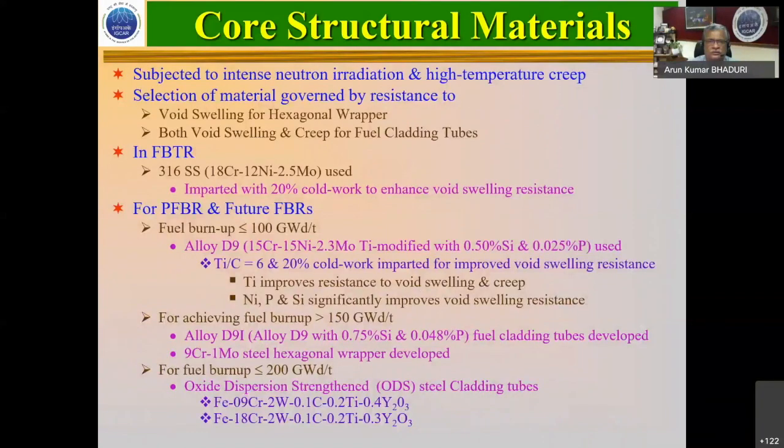The major problem with the core structural materials is that they see high temperature and creep, but also very intense neutron radiation, leading to significant radiation damage — void swelling in the wrapper, irradiation creep, and thermal creep in the fuel cladding. The FBTR, set up with French collaboration initially, uses indigenous fuel made by BARC — a mixed carbide fuel — with 316SS at about 20% cold work with dislocation density to reduce void swelling. For PFBR, with a slated burn-up of less than 100 gigawatt-days per tonne, we use a 15Cr-15Ni-2.3Mo titanium-added alloy with silicon and phosphorus — Alloy D9 — with a titanium-carbon ratio of 6 and 20% cold work for void swelling resistance.